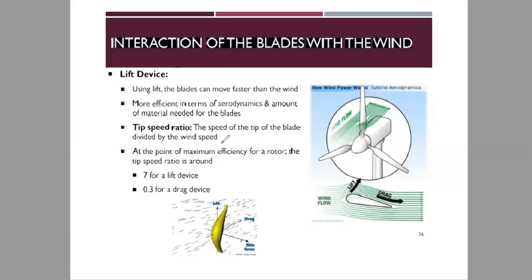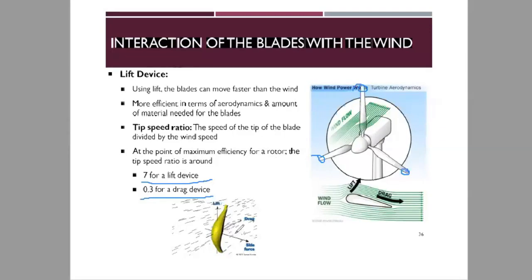The tip speed ratio is the speed of the tip of the blade divided by the wind speed. At the point of maximum efficiency for a rotor, the tip speed ratio is usually 7 for a lift device and 0.3 for a drag device. This shows the significant difference in performance between the two types.